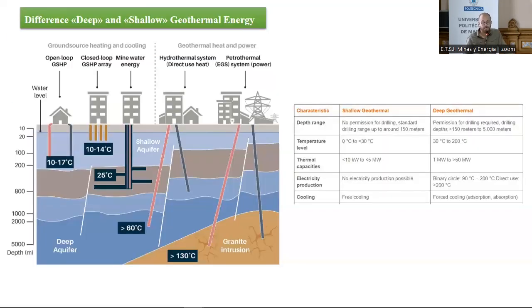Another difference is cooling. If you use a ground source or groundwater heat pump system in your building, you can achieve passive cooling in summer, because the soil temperature is around 13 Celsius, for example in my city Kutahya, while room temperature is 25 Celsius. So even if the system isn't running, there will be passive cooling: you bring the 13 Celsius soil temperature into your home and circulate it, without the heat pump working, and then inject the antifreeze fluid back into the soil. This is a passive cooling option for shallow geothermal energy.